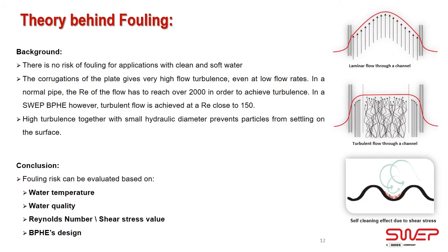For fouling, as for freezing, I think it's important to understand the theory behind it. From your point of view, is there a risk of fouling for application with clean and soft water? For sure, no, but unfortunately it doesn't exist in our industry. So one of the most critical parameters to evaluate the risk of fouling for a heat exchanger is the level of turbulence inside the heat exchanger. The higher the level of turbulence, the lower the risk of fouling due to the self-cleaning effect. But is there any difference between heat exchanger technologies? Yes, of course, otherwise it would have been too easy.